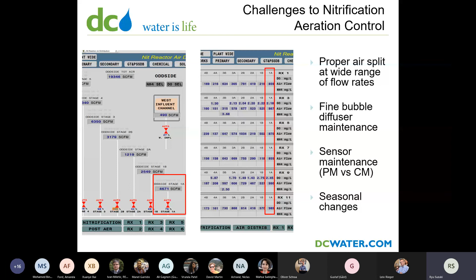So another major system limitation that we have is these 2 massive blowers. There are 2 4,000 horsepower blowers. The air demand for the nitrification system is actually only about half, 40 to 60% of the blower output. And a good chunk, about half the air, goes to miscellaneous uses, the big other, which is like the post-anoxic aeration, a lot of the channel mixing, and maintaining the final effluent aeration. So in a way, no matter how much we try to optimize the air demand in nitrification, we've actually gotten a much bigger bang for the buck by just avoiding air wastage in other places.